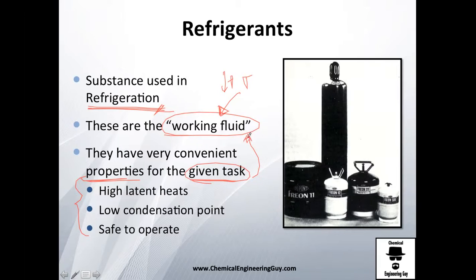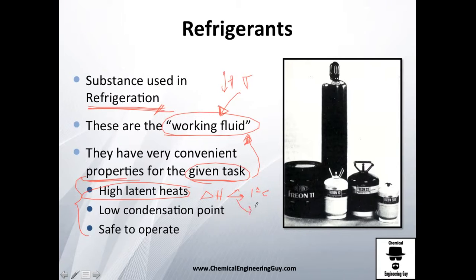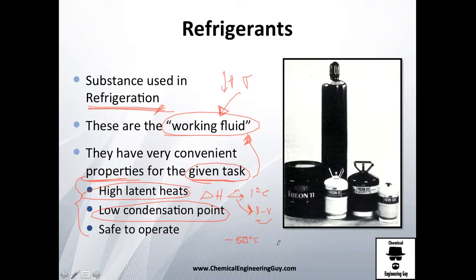Refrigerants have high latent heats, meaning they can hold a lot of enthalpy and require significant enthalpy changes to increase one degree Celsius or to change phase from liquid to vapor. They also have low condensation points — you may be operating at around 20°C rather than minus 50°C — which is normal and safe. Ideally, they are chemically inert: they won't oxidize and won't explode.